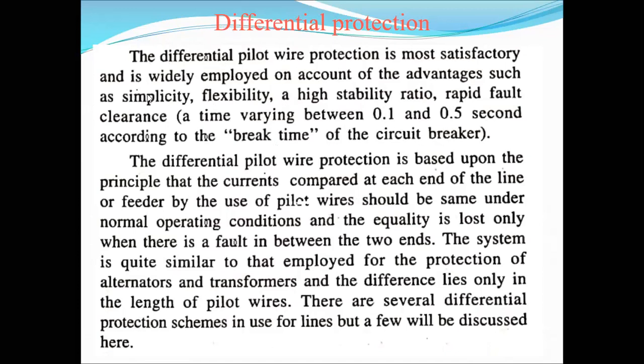According to the break time of that circuit breaker, it is 0.1 to 0.5 seconds. The differential pilot wire protection is based upon the principle that the current is compared at each end of the line or a feeder. What is meant by differential protection?